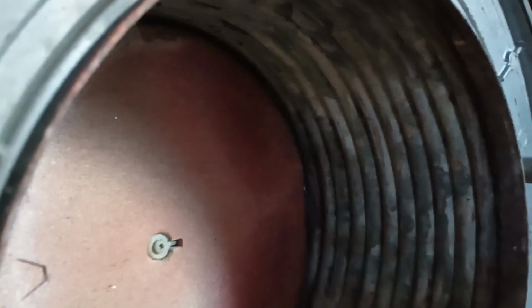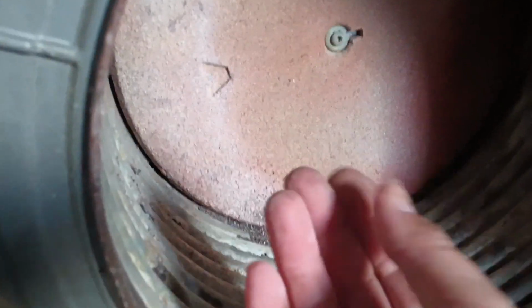And again, this is how corroded that burner was. On the inside, it's actually not too horrible. This would be the bottom of the heat exchanger. You can see a bunch of oxidation up in here. But somebody at least has cleaned it. I've seen a lot worse. Usually you get a lot of this black, carbony looking material built up inside of there. But of course, this boiler's been bounced around loading docks, I don't know how many times.